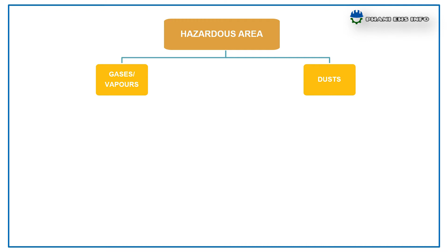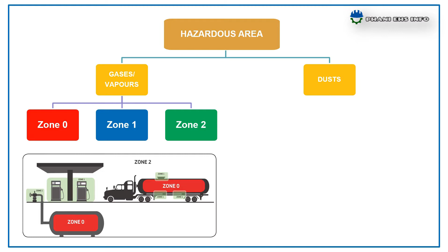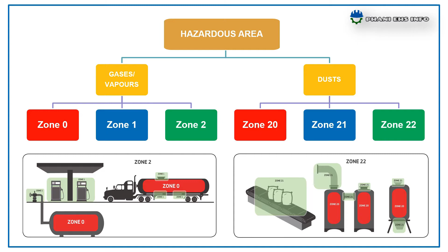Next one, hazardous area classification. Hazardous areas are classified into two major categories: gases or vapors, and dusts. Under gases or vapors, hazardous areas are classified into three different zones: Zone 0, Zone 1, and Zone 2. Similarly, dusts are classified into three different zones: Zone 20, Zone 21, and Zone 22.